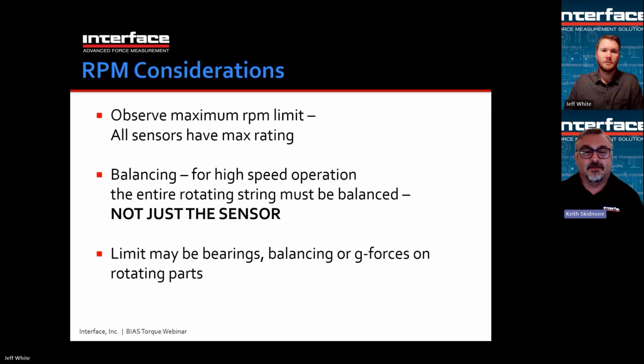So the ratings are typically maxed out as they are on the data sheets, and they don't have any extra wiggle room. Some of the things too have to do with bearing life. And if you talk to a bearing manufacturer, how long is my bearing going to last? They won't tell you. There's all kinds of variables. So RPM is one of them. Load, heat, lubrication, all of those things come into play. And so the ratings listed on the data sheets are intended to allow the sensor to operate under those RPM conditions for a good long lifetime without wearing out the bearings.